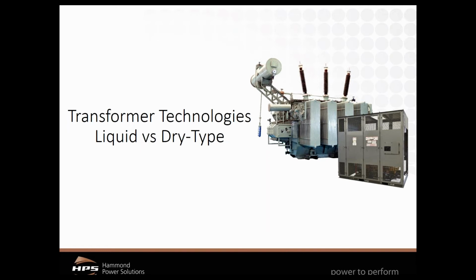One of the big reasons why we're having this presentation right now is because this topic has become very topical, mainly because lead times for power transformers have gone out, and in some cases we're seeing lead times for liquid type transformers at 1 and even 2 years. As a result, some people are looking for alternatives, and one of the alternatives people are looking at is dry type. And one of the things that we want to get across today is that both technologies are very good technologies, and there are pluses and minuses for both technologies. However, there is no dry type equivalent for a liquid cooled transformer, and there's no liquid cooled equivalent to a dry type transformer. They both can be used oftentimes in the same applications, but things like site preparation and specifications definitely have to be adapted to both technologies.